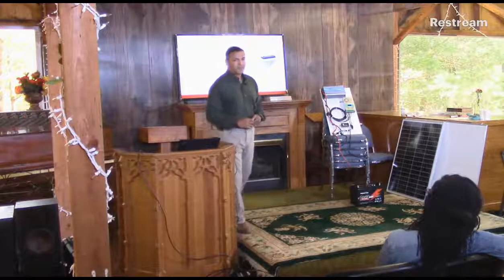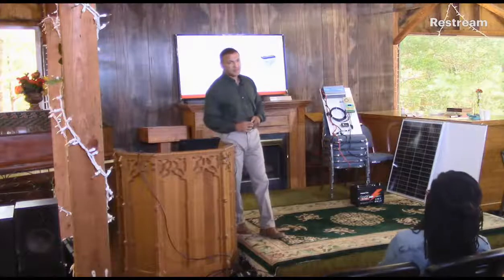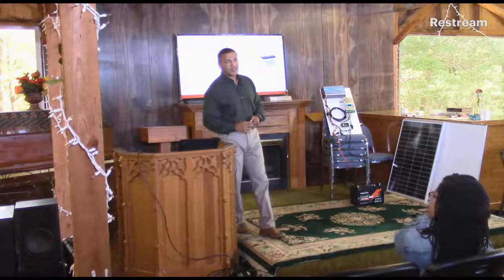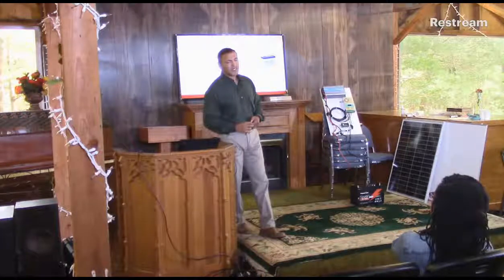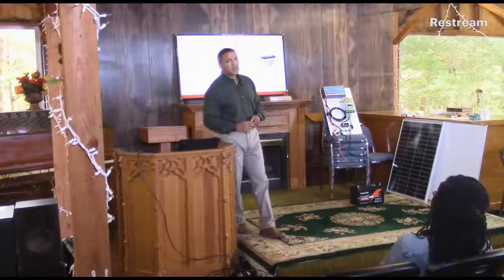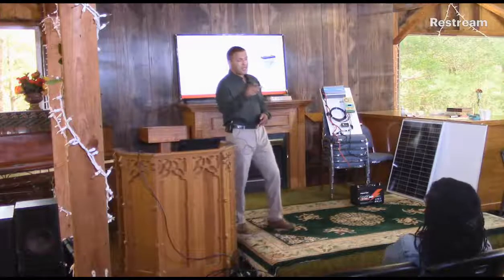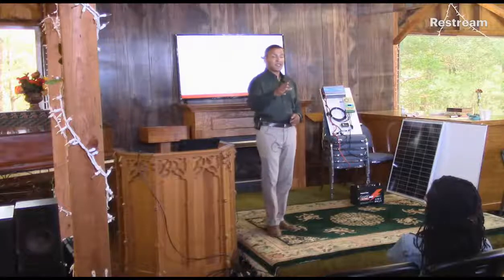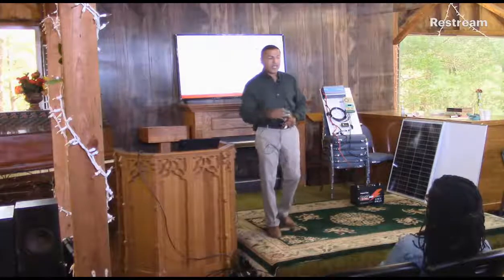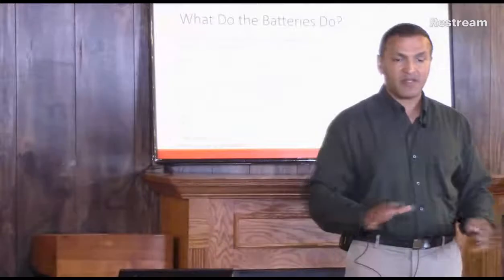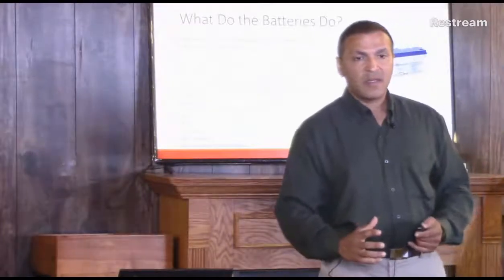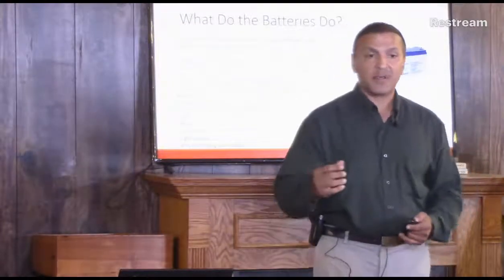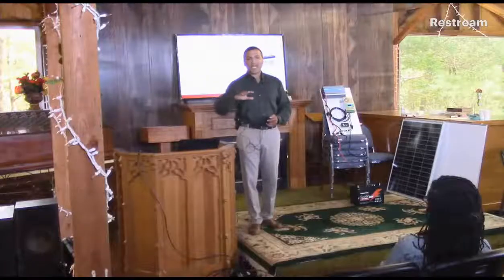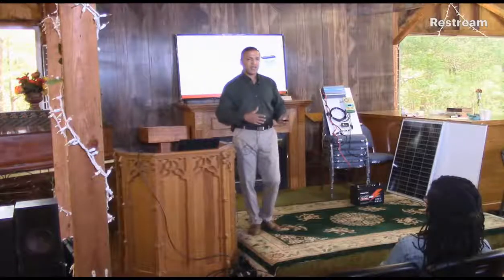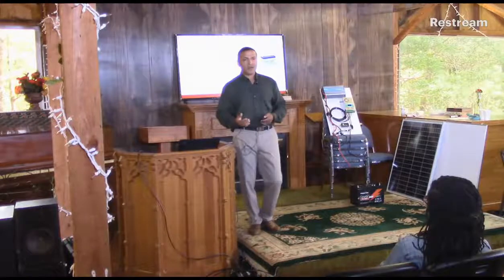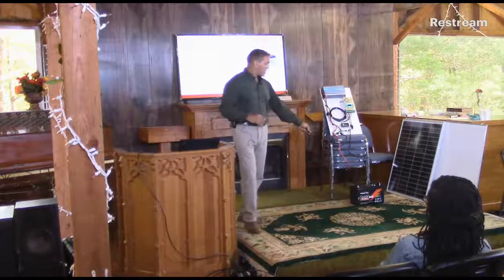So my understanding about the other type of batteries you were talking about, lead acid batteries, is that they have cells and you have to fill them. Those are the flooded lead acid batteries. But you also have sealed lead acid batteries, like AGM or gel, which don't need to be maintained since they're sealed. Some people still use gel, but most are moving to AGM sealed or flooded batteries, those are the typical two on the market right now. With lithium iron phosphate batteries, though...